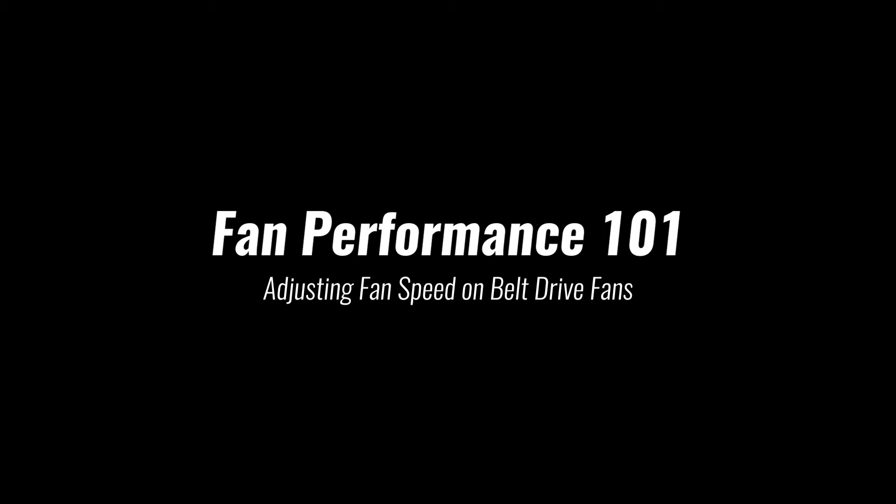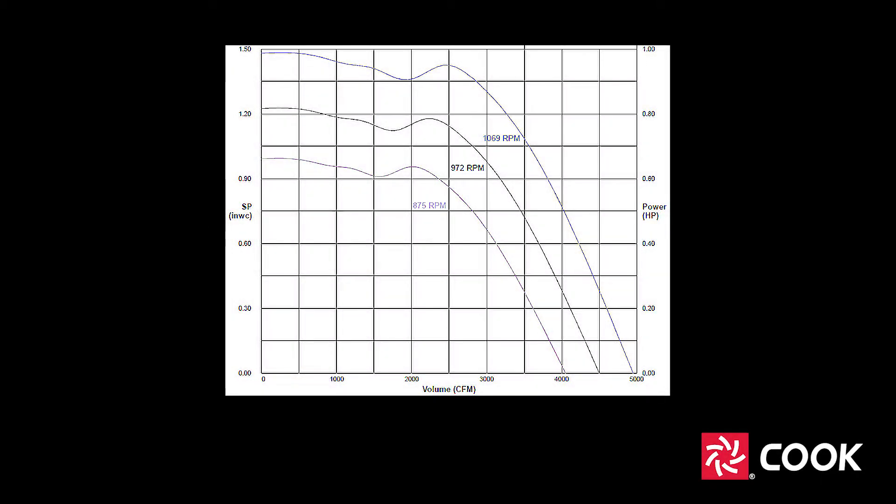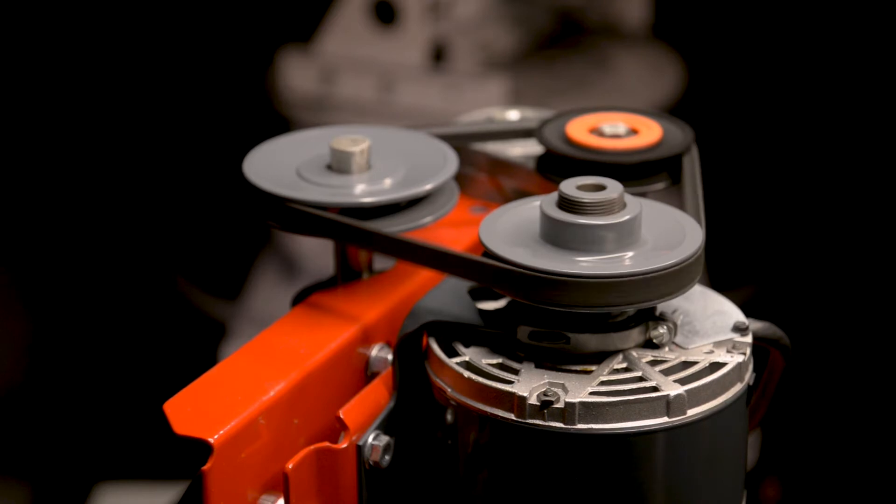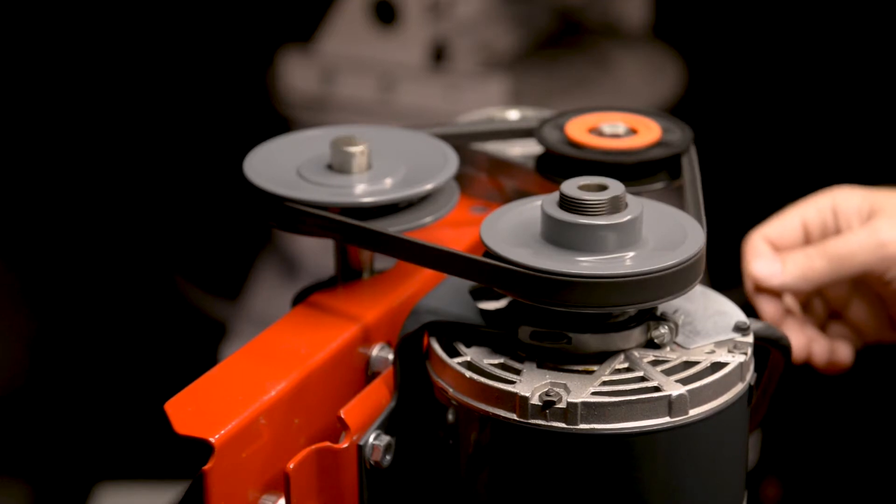Fan speed, how fast the fan impeller rotates, is a key factor affecting fan performance. As you can see from this typical performance fan curve, as the speed increases the fan is able to deliver more airflow and develop more pressure. The fan speed here is indicated as fan RPM or revolutions per minute. Understanding how to set or change fan speed for a belt drive is an essential part of ensuring proper fan performance. Let's see how this works.